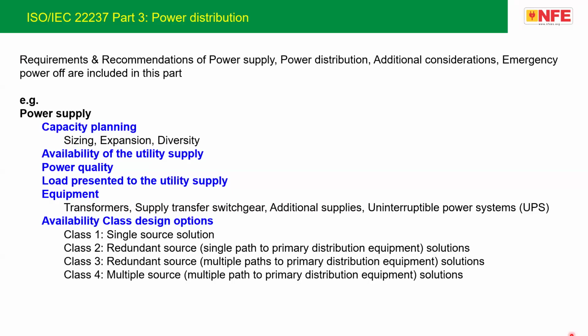And during inspection, we have to connect a load bank for the 3 megawatt DG set and test it. That load will be additional for the system, which will be required for the UPS when we go to bypass mode. So that also has to be taken care of. This is the requirement for the sizing. Now the next is expansion. We should also take care of the expansion required between the initial load and the maximum planned load, while maintaining optimum efficiency.